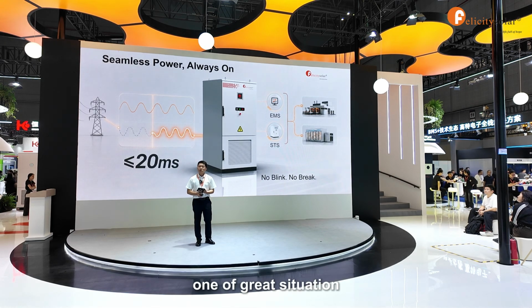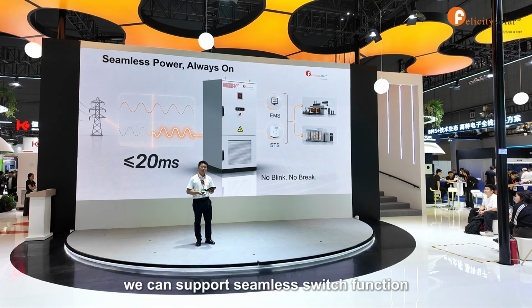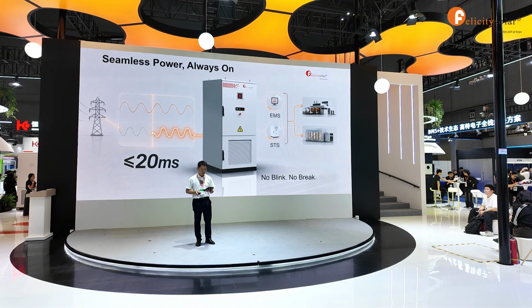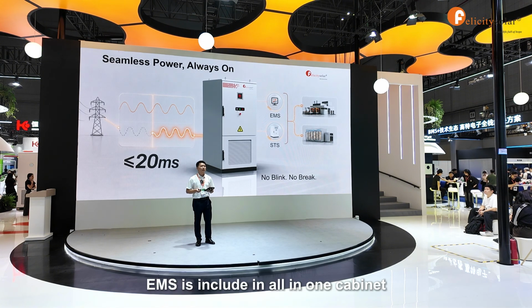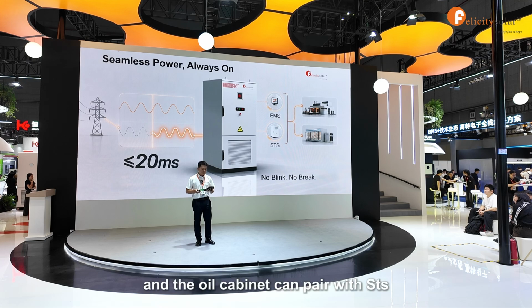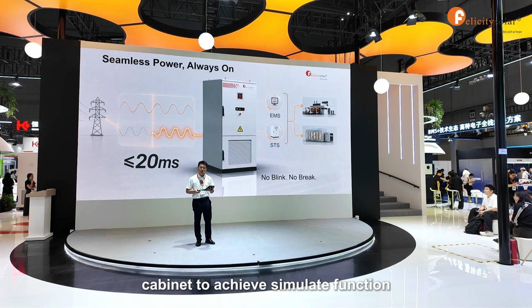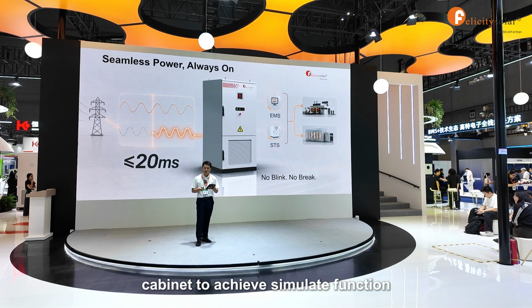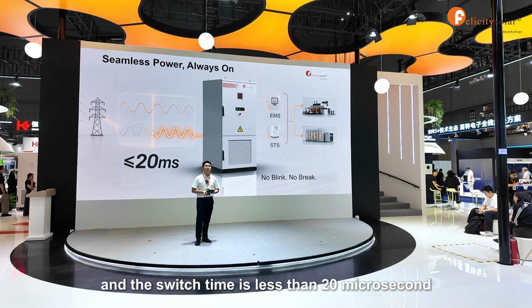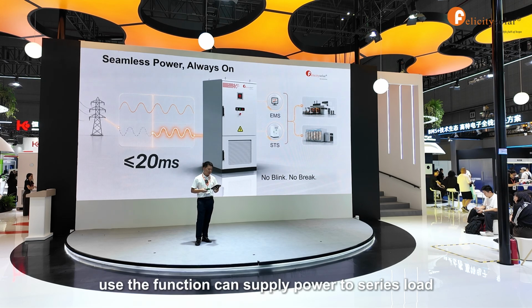In off-grid situations, we can support seamless switch function. EMS is included in the all-in-one cabinet, and the all-in-one cabinet can pair with the STS cabinet to achieve the seamless function, and the switch time is less than 20 milliseconds. Use the function and supply power to serious load.